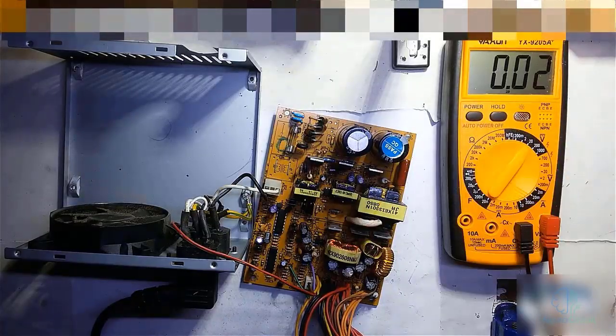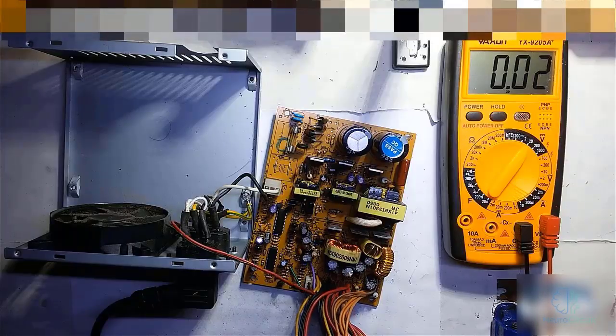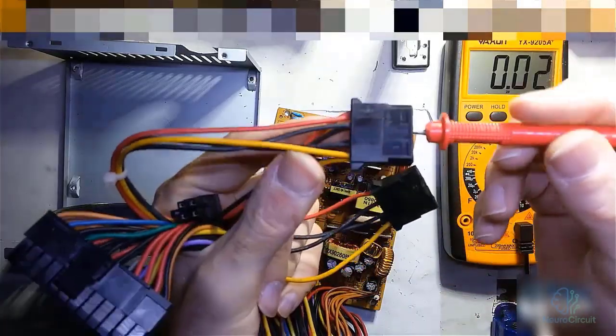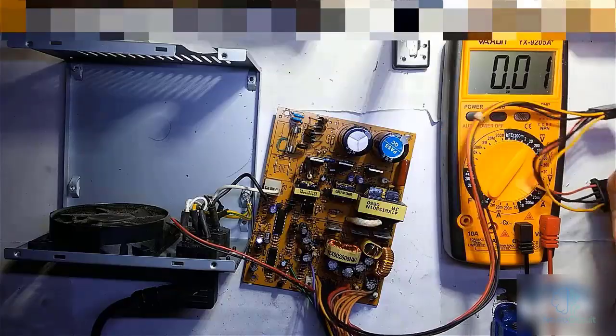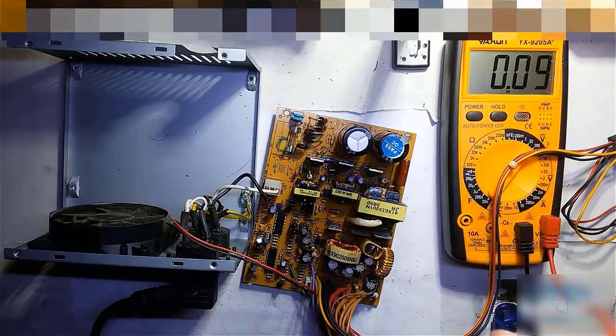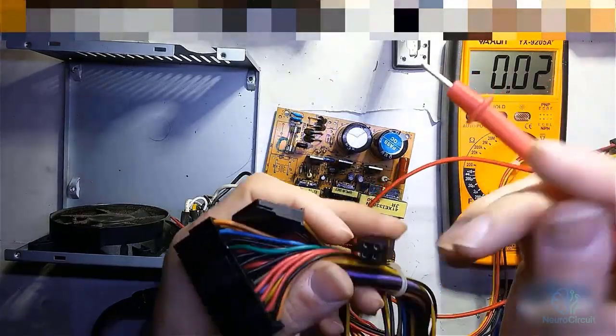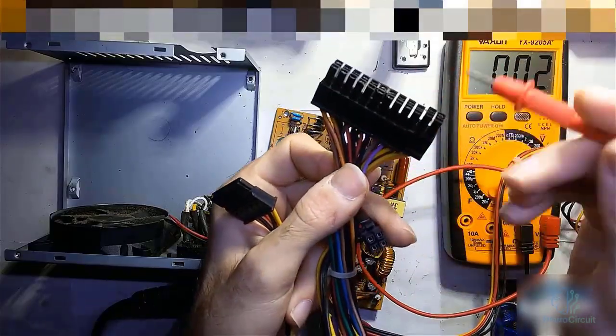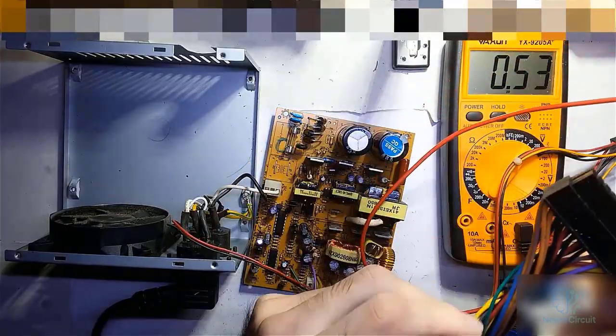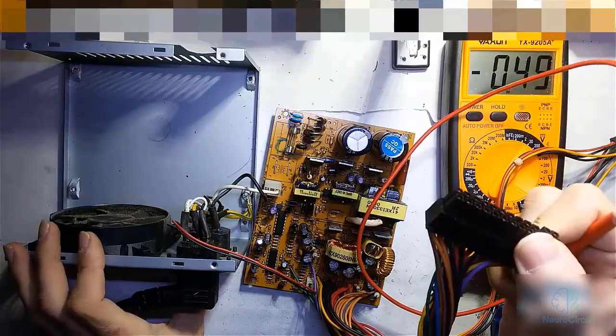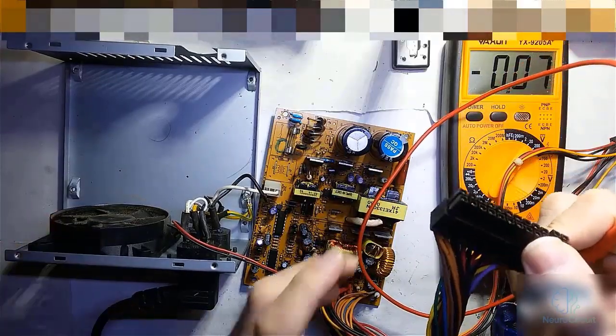We'll set the multimeter to the DC voltage range, then connect the black probe to one of the black wires to ensure a proper connection for accurate voltage measurement. We'll position it here, then using the red probe, the positive probe of the multimeter, we'll check the voltage on the purple wire to determine if the standby voltage is now present. Alright, let's plug in the power supply and power it up.